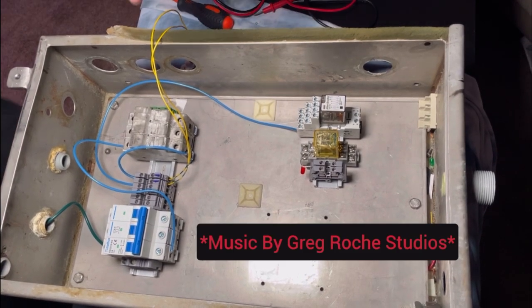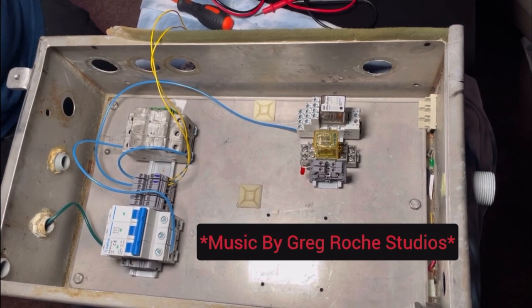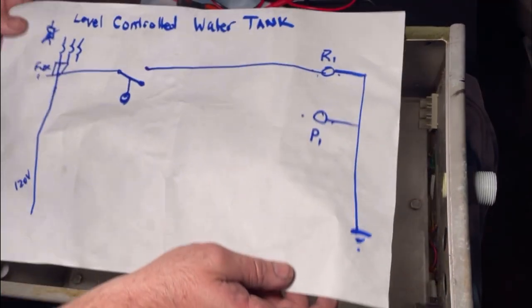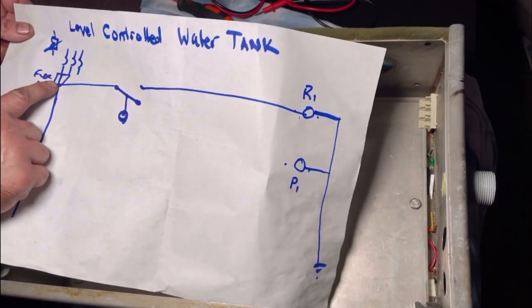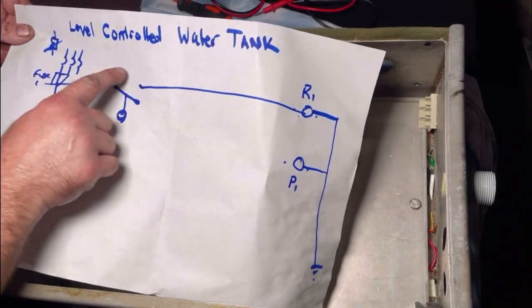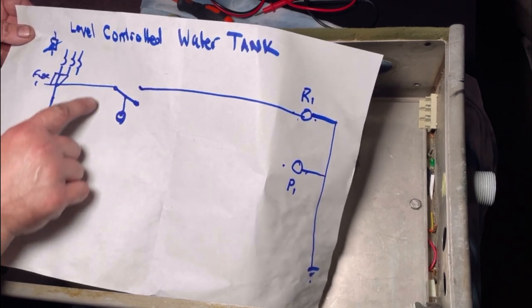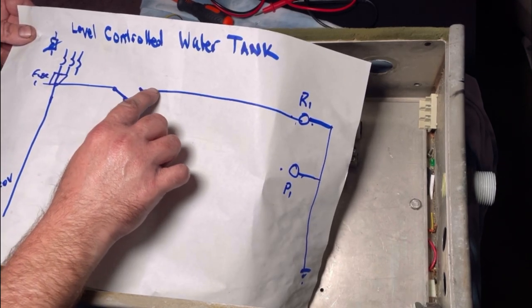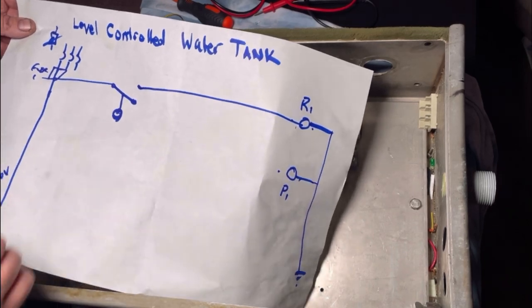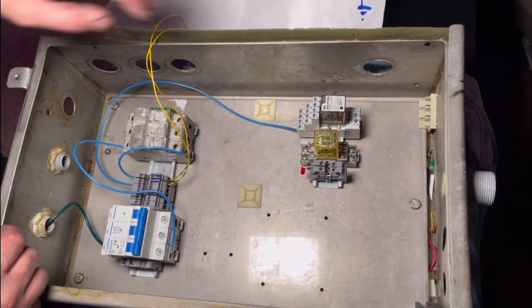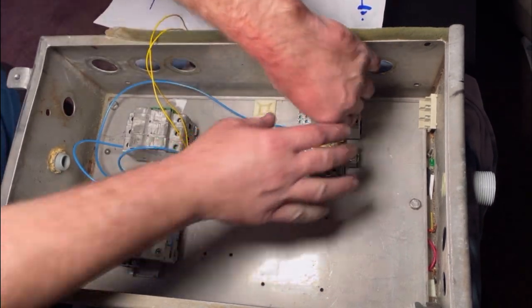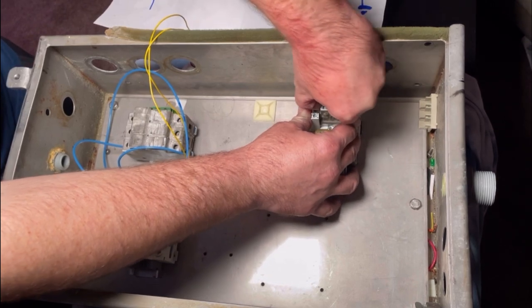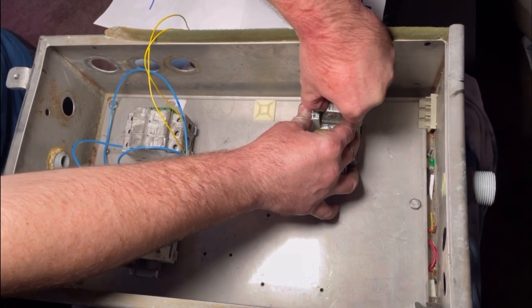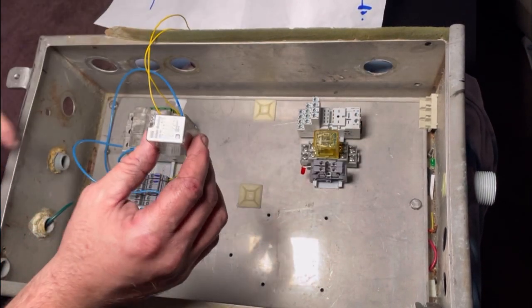Okay, so up to this point I've wired in my float. Pull this schematic up to show you guys. Circuit breaker through a fuse to a float. We're going to verify that it's a normally open float here in a second. And then we're just going to run that over to relay 1. Relay 1 is one of our loads. So in other words, it's a device, it's an output.